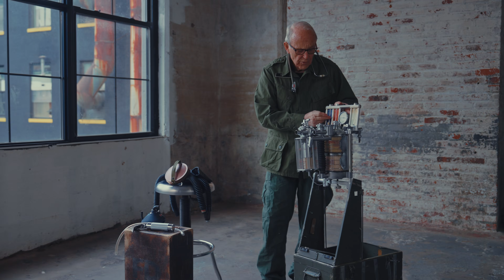These are the flow meters for nitrous oxide, for a gas called cyclopropane, which is no longer used anywhere in the United States for anesthesia. This is the oxygen gas in the back, or the attachments for the cylinders that hold the oxygen and the nitrous oxide, and they would be stored here, and then a special attachment that comes and holds onto here. The front part of the anesthesia machine has valves so that the gas, the anesthetic gas, as well as the oxygen, can only go one way. You then attach this to here, and this is the resuscitator bag, and it is attached here.